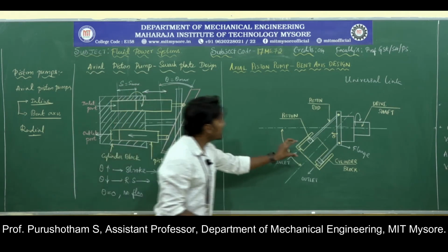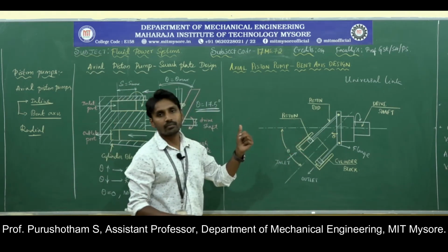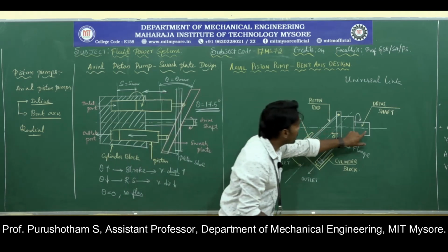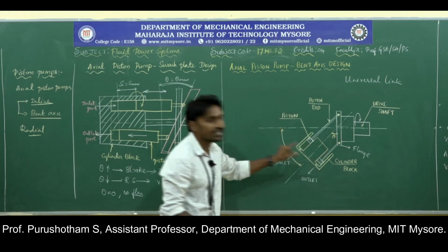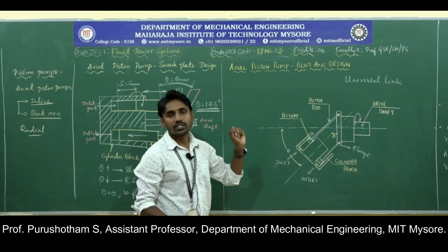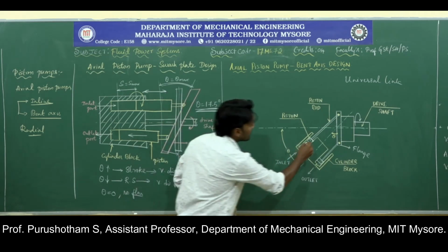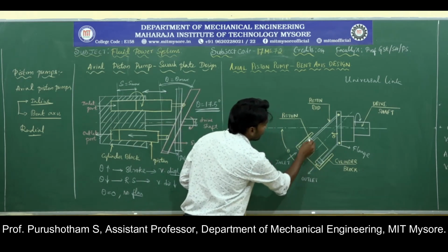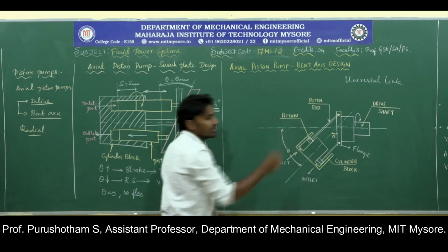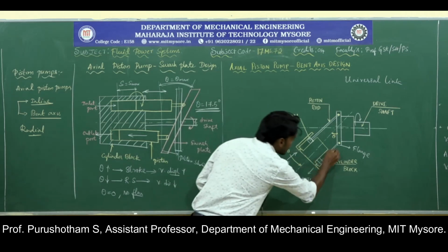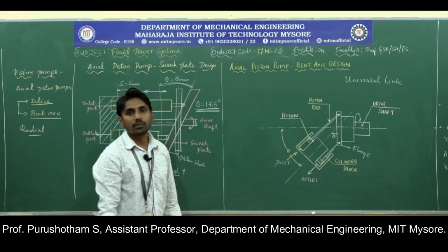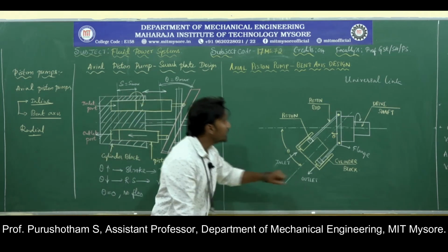When the cylinder block rotates, due to the offset angle of the driving shaft flange and the cylinder block, the piston starts to reciprocate. When it retracts, the oil enters the chamber; when it extends, the pressurized oil is ejected out of the chamber.